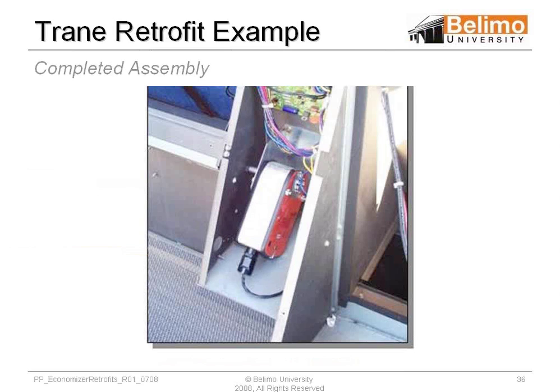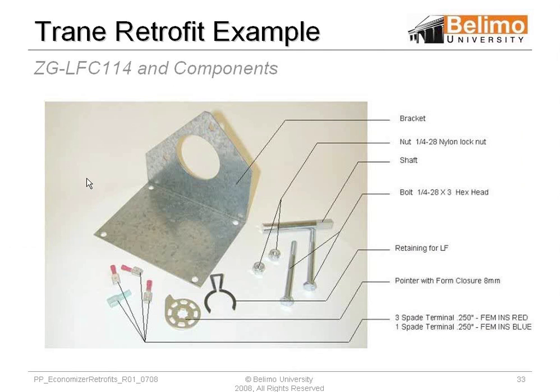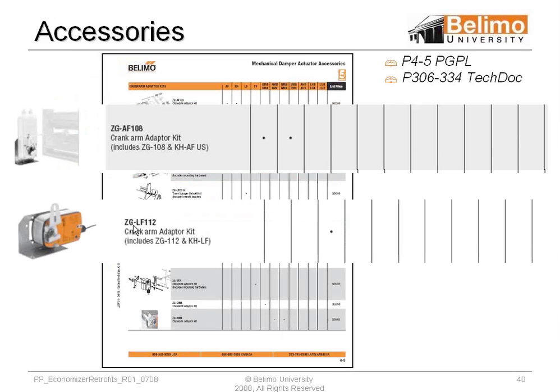There are some pictures here. We can do Trane retrofits — we use different types of brackets with the LF or AFs. Going through the accessory pages, you can pull out a crank arm. The designation gives you the ZGAF US and ZGLF US for the AF and the NF. The ZGAF 108 and the ZGLF 112 are probably the most popular ones and handle a majority of retrofits.